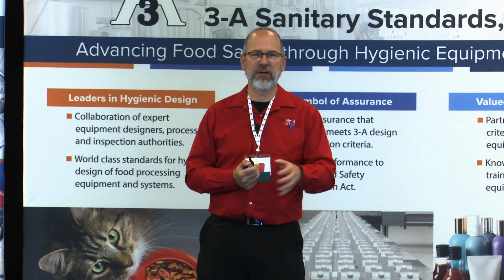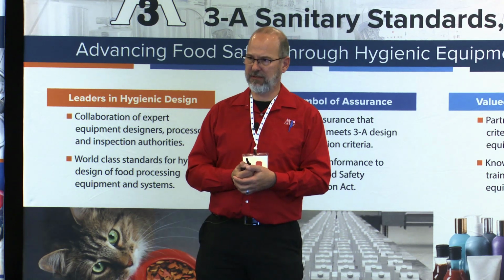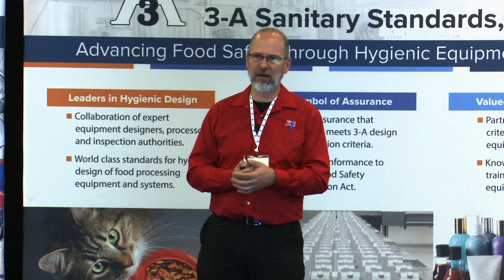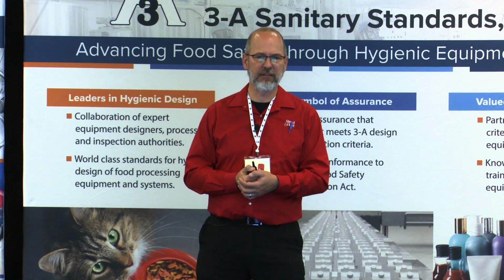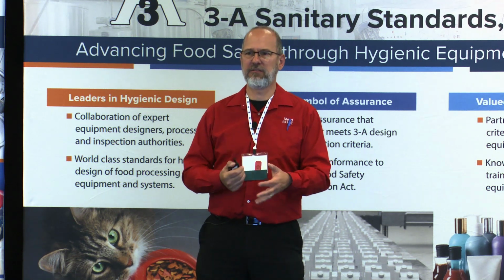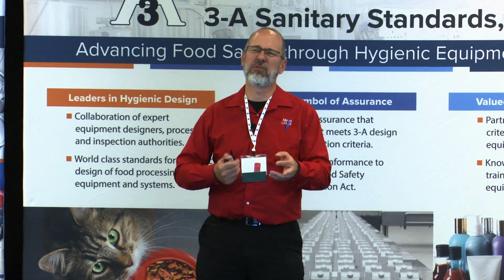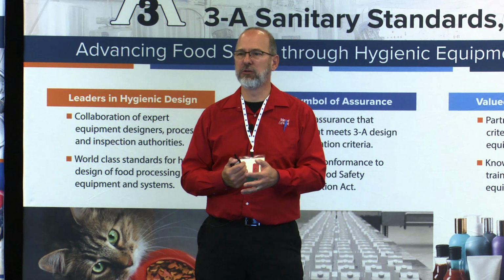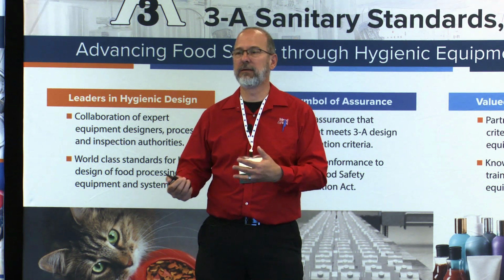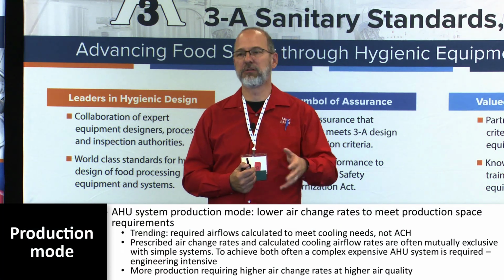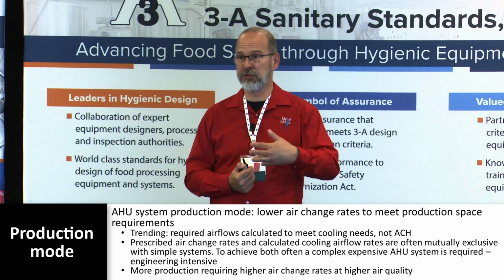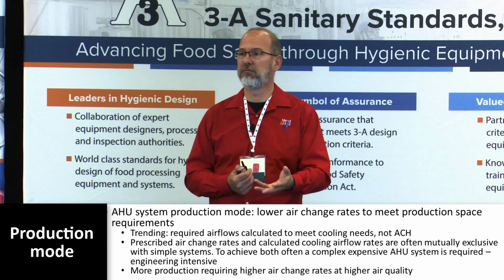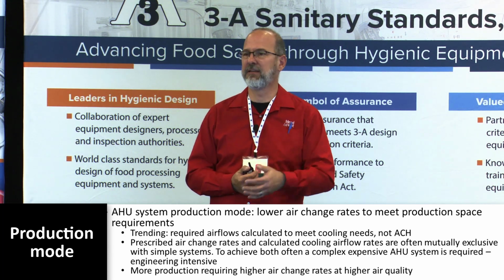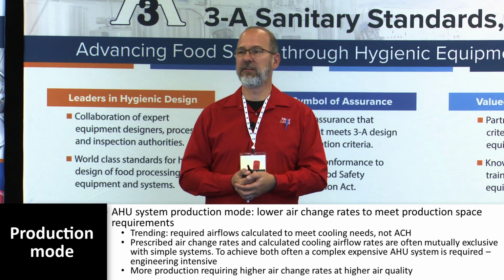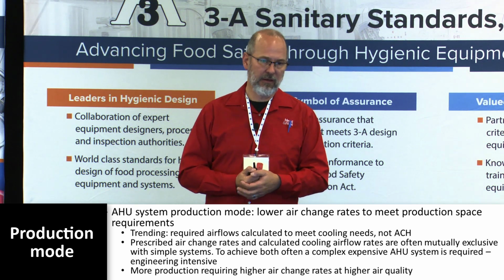Typically, there's a lot of different ways you can design these air handlers to operate in a space, but the most common way I see is to design these HVAC systems with primarily two operational modes, a production mode and a cleanup mode, where in production mode you're making food product and the unit just runs to heat, cool, and filter air, just maintaining the temperature and humidity set points you need in the space.